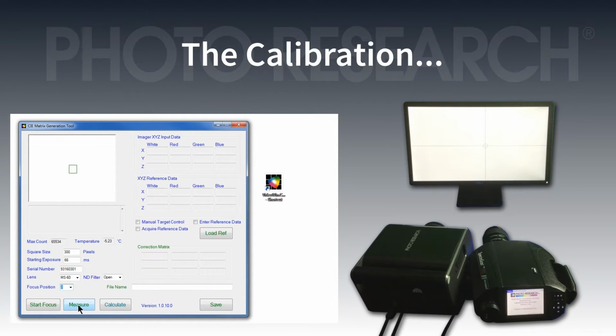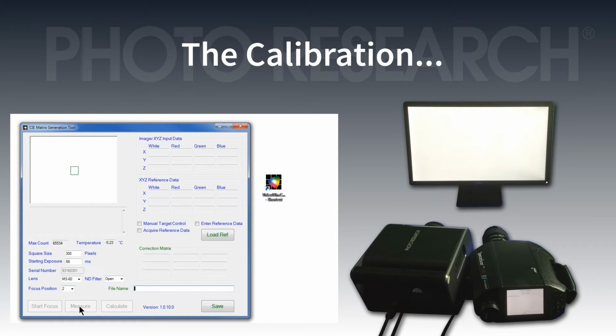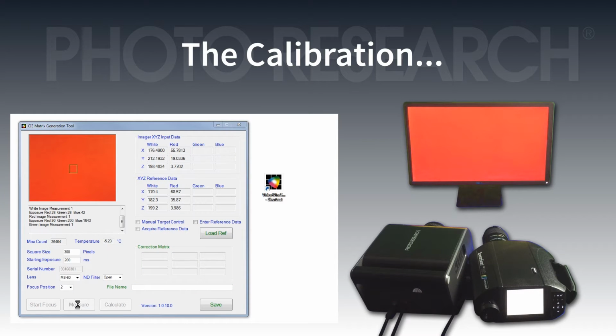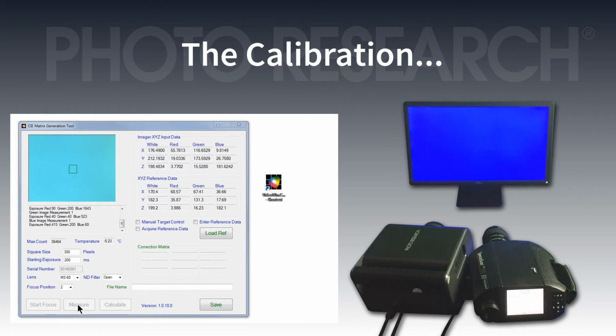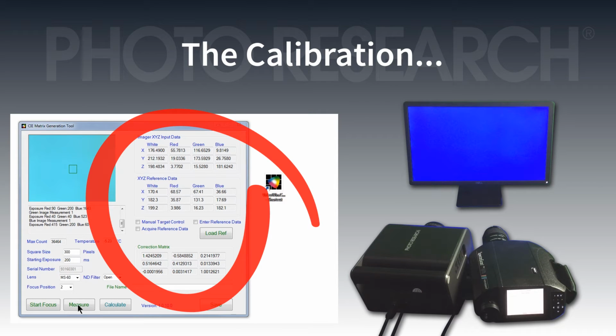Now we are ready to start the calibration. Click on Measure. The process begins by first measuring a white screen with the spectroradiometer, then with the imager, then a red, green, and blue screen with both instruments. When the sequence is complete, the imager XYZ input data, XYZ reference data, and correction matrix fields are filled in.